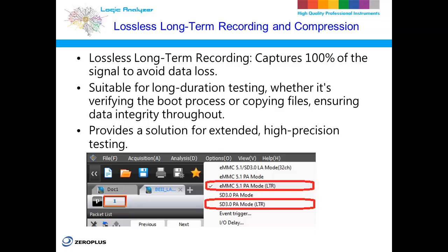extended periods. In traditional setups, during long-duration recordings, some signal data may be lost due to limitations in storage performance or the USB device's handling capacity. This can negatively impact the accuracy of the test results. However, the lossless long-duration recording feature ensures that all data paths are validated before recording, guaranteeing that every signal is captured completely without any omissions. This helps maintain data integrity throughout the testing process.